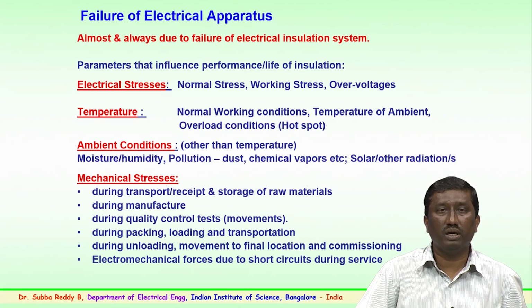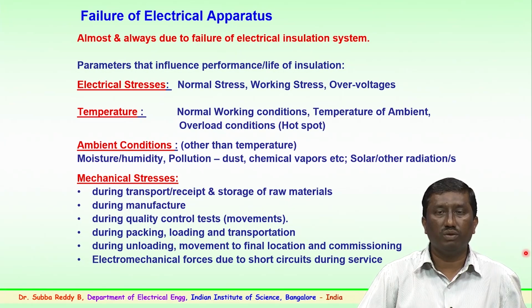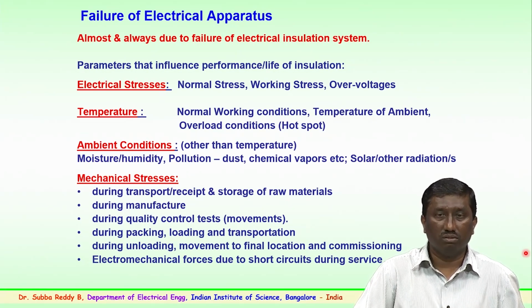So, apart from electrical and ambient conditions, there are the mechanical stresses, particularly those which the insulation, component or insulator sees during transportation, storage of raw materials, the manufacturing process, quality control testing, movements at various locations in the industry, packaging and loading. All this could lead to mechanical stress on the product where the insulation could be affected. Apart from this, there is normal loading and unloading of the material, movement to the final location, and commissioning. Several of these factors influence the insulation, apart from the electromechanical forces which could be due to short circuits during service.